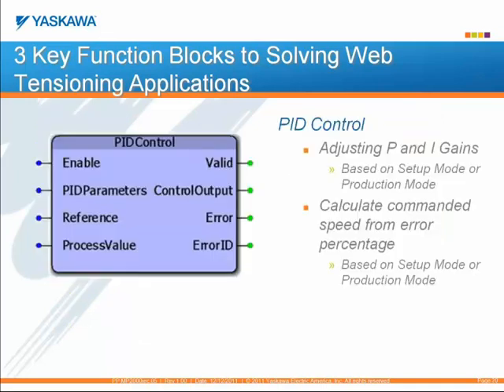The PID control function block is used to adjust gains based on setup of machines. A system can have two modes: a setup mode where tension is built up for running a machine, and a production mode where tension is maintained while running. This function block is handy for tuning — it can be added to the watch window and monitored, and different sets of gains can be loaded in depending on the system.